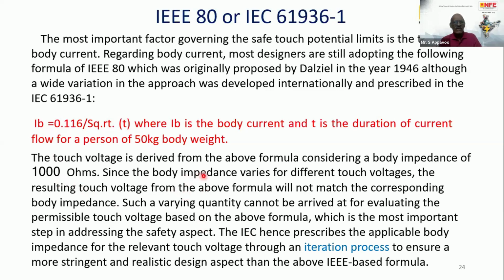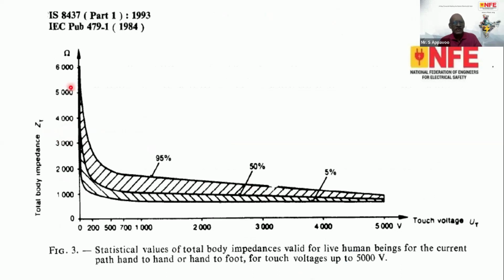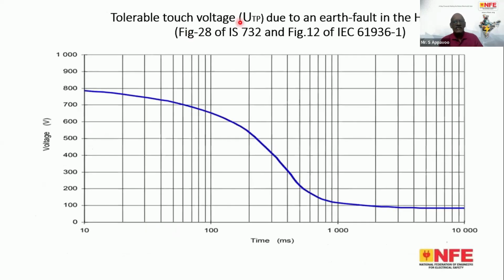And modern concepts have evolved according to these concepts. For example, if you see how body impedance varies, at 200 volt it exhibits 4,000 ohms, and at 1,000 volt it exhibits less than 1 kilo ohm. So we have to take into account these factors. That is why the standard IEC 61936, under figure 12, which is nothing but figure 28 of IS 732, provides a curve. This is the important thing. For example, if the fault clearing time is 200 milliseconds, the touch voltage should be restricted to say 550 volt. So depending upon the fault clearing time, we have to design the installation.